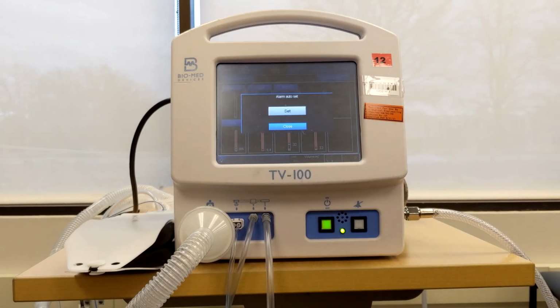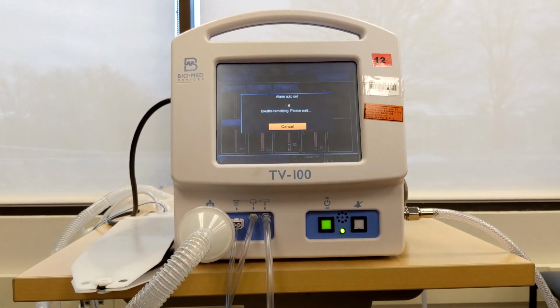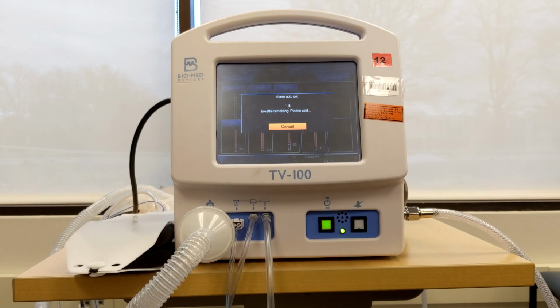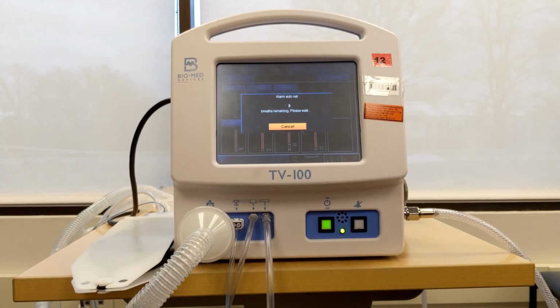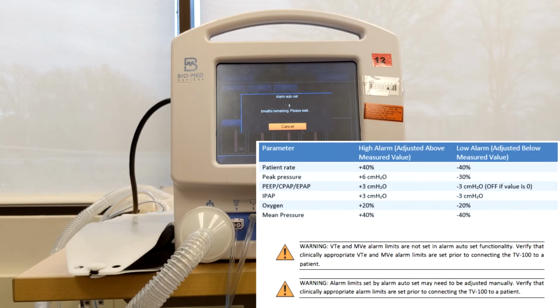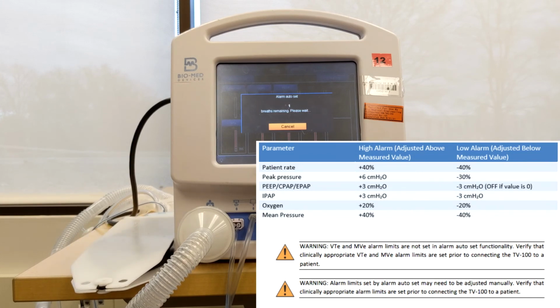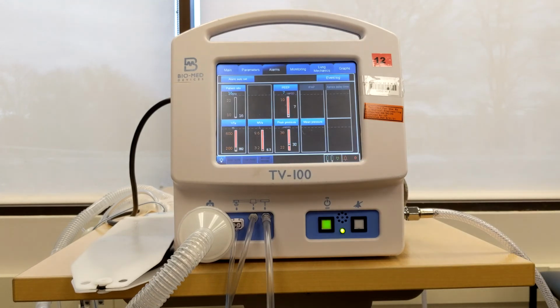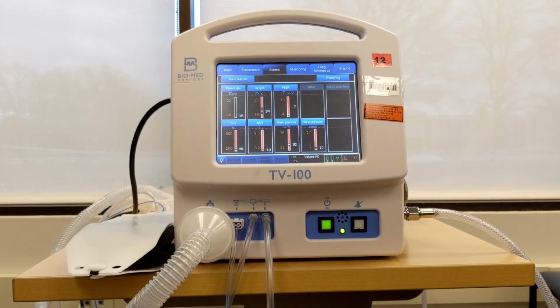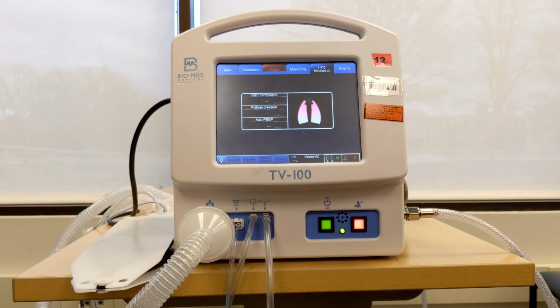When you press the Set button, the TV-100 will begin to set the alarms. The TV-100 will take 5 sample breaths, then calculate the necessary values to balance the alarm limits. The TV-100 will calculate the following parameters for the Alarm Auto Set. When an alarm condition occurs, the TV-100 will blink the alarm parameter that is out of limit on the alarms page. The physical alarm button will blink, and the TV-100 will sound an audible alarm.